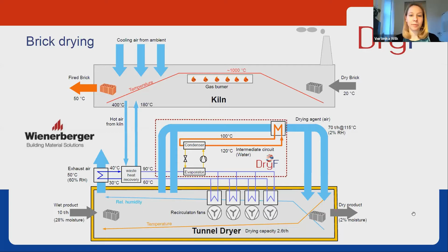And in that sketch, you also have the temperature profile of the tunnel dryer. So we start at lower temperature and reach higher temperatures in the final drying zone to really ensure to reach that final residual moisture content. And the air and the bricks are moving countercurrently. So the air is fed at the final end, moving through the dryer in a countercurrent flow. Our heat pump is also using that waste heat recovery cycle and is integrated. So the evaporator is integrated before the drying surface, the heat exchanger for drying within the tunnel. And there's a recirculation airstream taking air from the front part of the dryer and moving it to the final part of the dryer. And there typically a gas burner is installed to increase the temperature, and this is where we have integrated the heat pump to heat that recycled airstream.